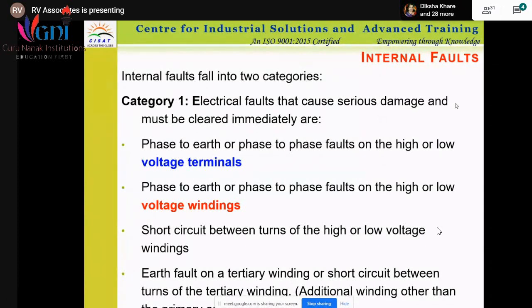Then there will be a short circuit between turns of the high or low voltage winding. Talking about high and low voltage winding, it means primary as well as secondary. There will be earth winding faults, and maybe if there is any tertiary winding in the transformer, in that case the failure will be again the same thing. It can be an open circuit, it can be a short circuit. So these are the internal faults of the transformer.